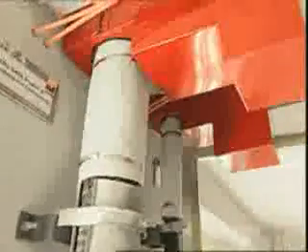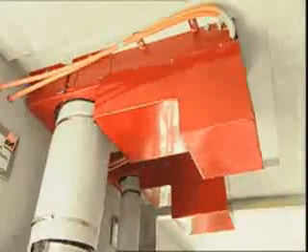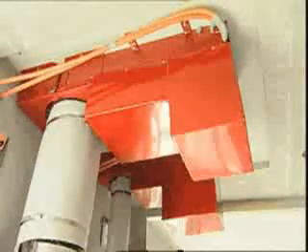The PYRO-SAFE power cut system seals broadcasting cables as well as combustible pipes. In a fire, a horizontal cutting mechanism separates the cables or pipes and at the same time seals the cross-section tightly. A spread of fire is thus prevented.